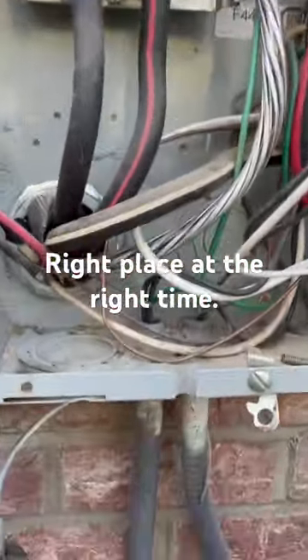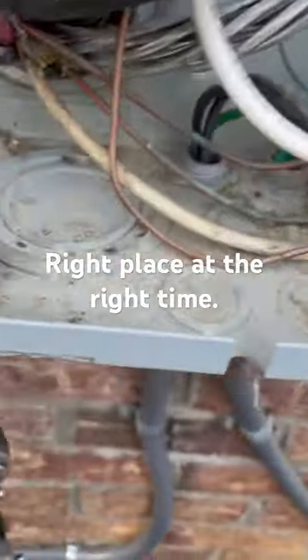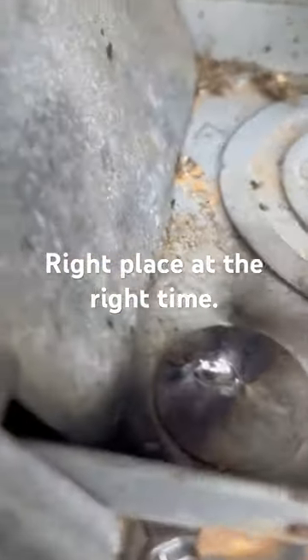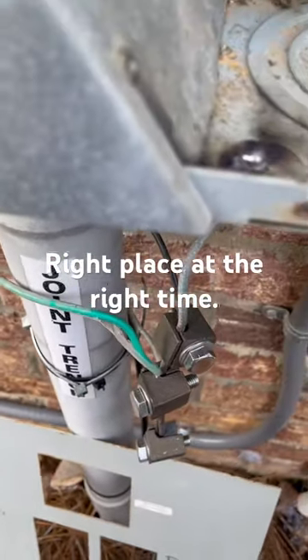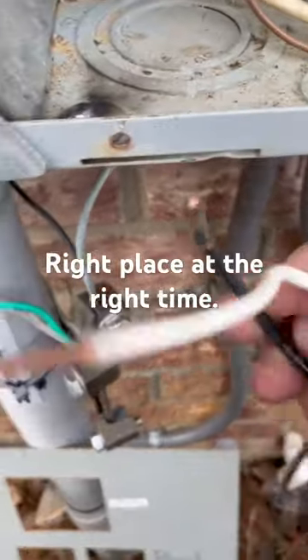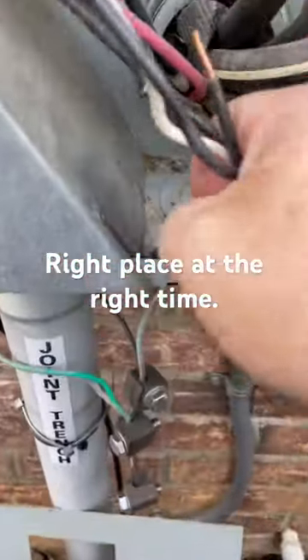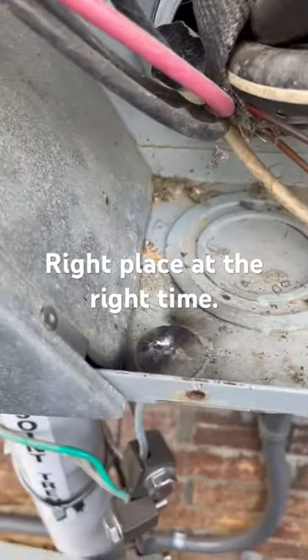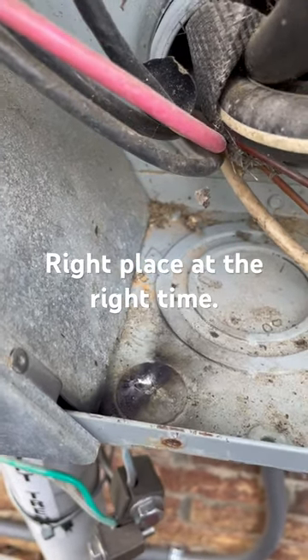If you're sitting out here, you've checked everything, you're getting ready to leave — and you hear a loud pop. This wire has been sitting in here rubbing against the inside of this panel and it burned up the end of the wire right there. They had all this wire crammed down in that corner and it's been sitting here rubbing all this time, and then just as you pick up your bag — bam. Gotta love it.